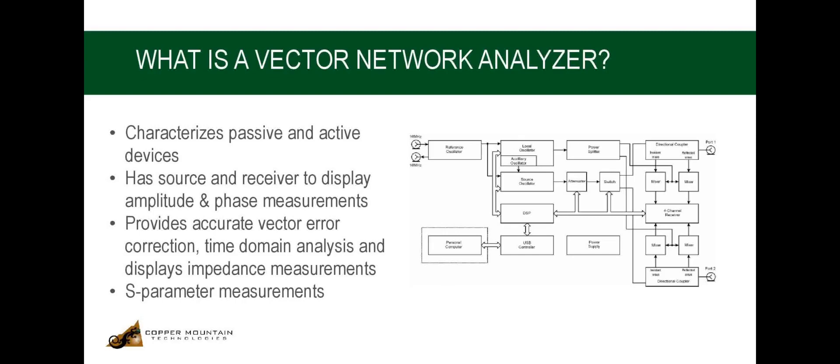The focus here is on accurate measurement of the ratios of reflected and transmitted signal to the incident signal. So, the instrument is always comparing the stimulated signal with the received signal. Also, the reason why vector measurements are important is because it is essential to have magnitude and phase to completely characterize a device.